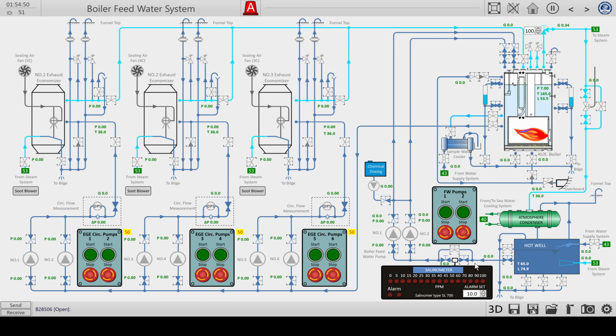Feed water - we were here, got the hot well at 75%. Two feed pumps should be turning on automatically, but we are at a high level. I'm not quite sure how I got into this situation with so much water in my boiler, but there's not much of a problem at the moment.